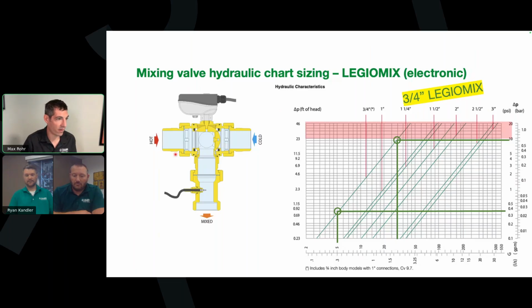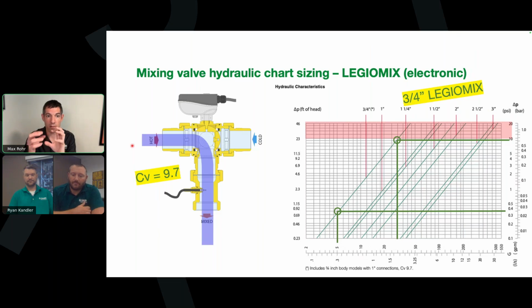And here's kind of the major difference. The C sub V for this valve is 9.7, even at 3/4 inch, but that's the flow path through here. So that's one of the things that in a training we like to point out: you can look into the port of a digital mixing valve and see a much different scenario than looking and seeing a bunch of different objects in the center of the thermostatic mixing valve. Again, neither of these is wrong. They will both mix water from 5 to 30 GPM in this scenario, but that's why you can go so much smaller with the Legio mix, the digital mixing valve, because it's a diverting ball essentially.